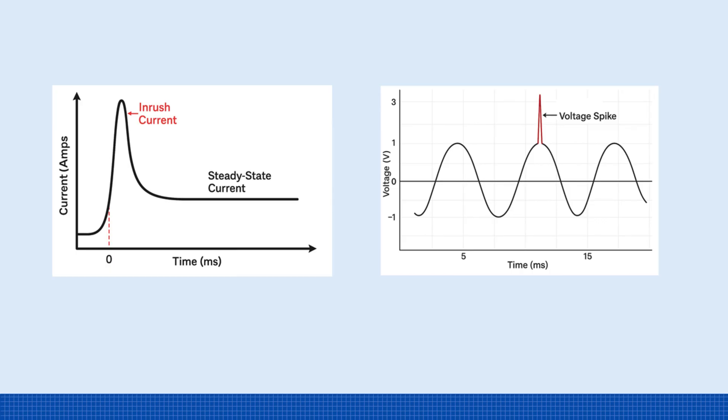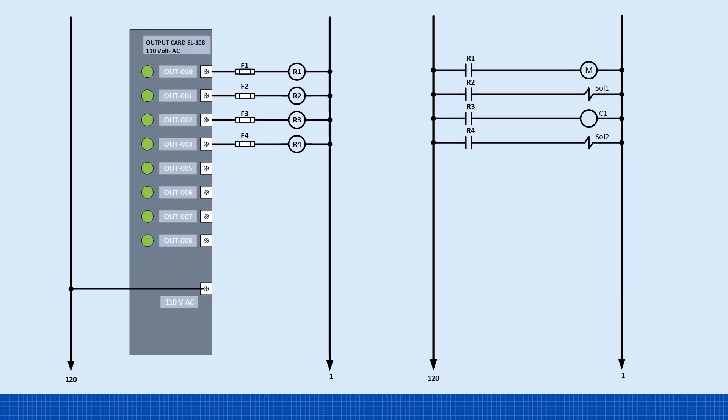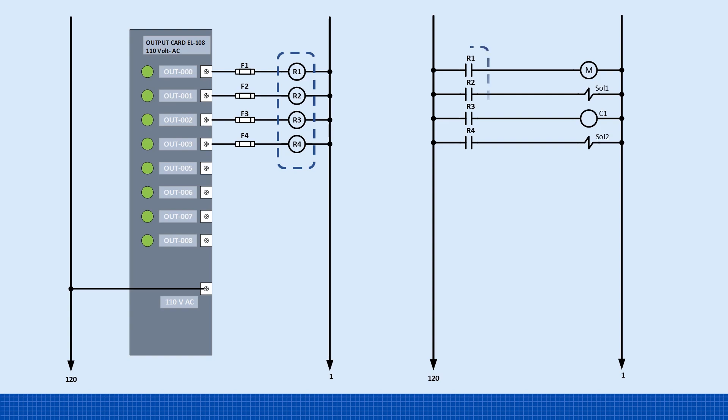A more reliable control panel design is to have the PLC output energize an interposing relay rather than powering high-load devices directly. These relays have small coils with low current draw and minimal inrush, making them much easier on the PLC's output card. Then, use the relay contacts to switch larger loads, like contactors, motor starters, or solenoid valves. This not only extends the life of your PLC outputs, but also adds a layer of electrical isolation.